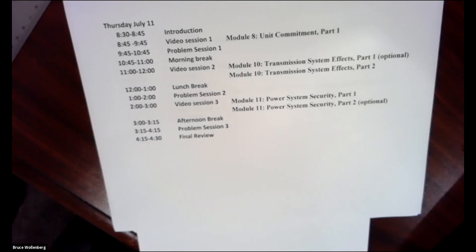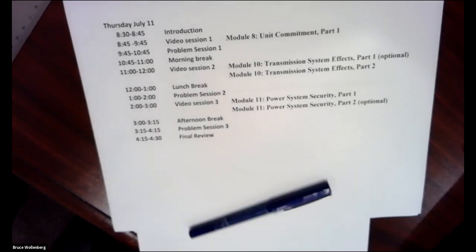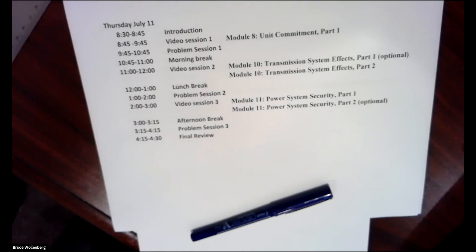In running one or two machines, in reality, there are other costs in addition to startup costs. Aging, absolutely right, which translates to more frequent maintenance and many starts and stops. This is an issue that system operators are reluctant to accept, but it is true. And it's one of the big problems today when you're using a conventional generator that's there to fill in when wind or solar is not generating, which tends to go up and down, so you need some sort of conventional. You might have gas turbines that come on. When they come on and start up and run up, and then they run down and turn off and so forth, those kind of rapid start generators, yeah, they have wear and tear on them.